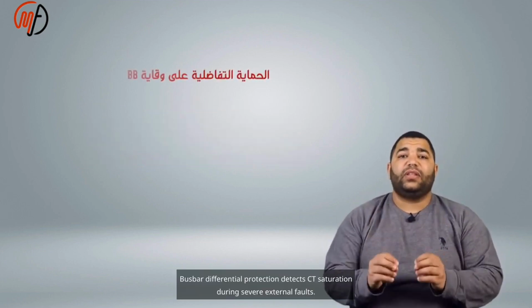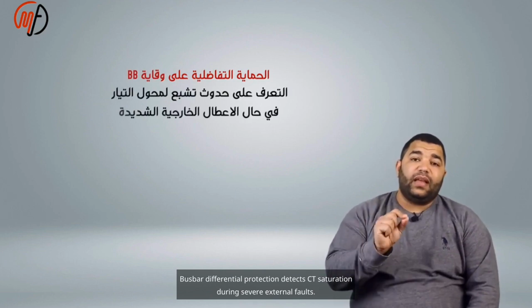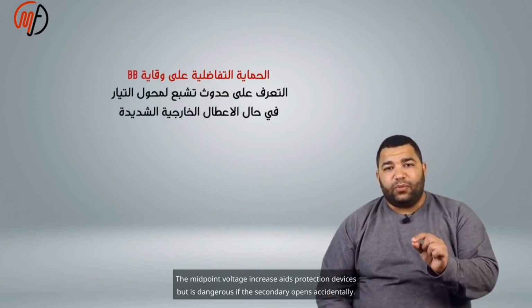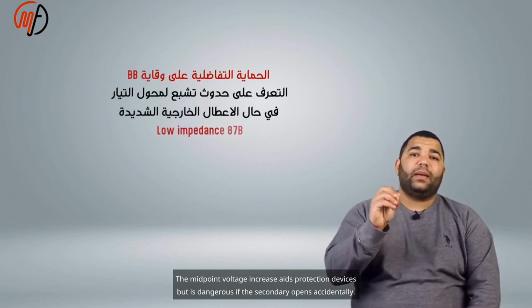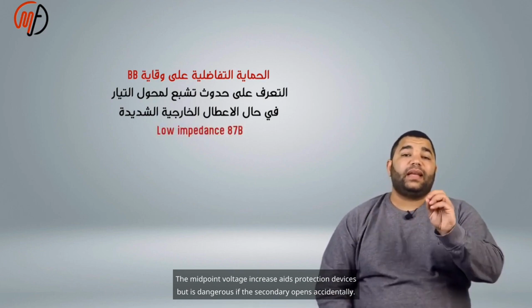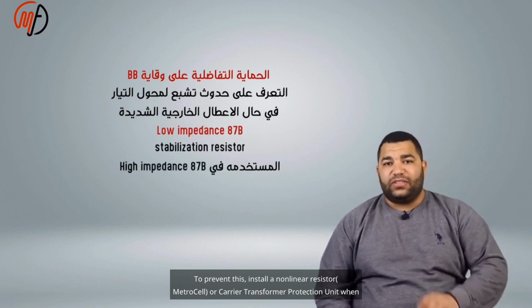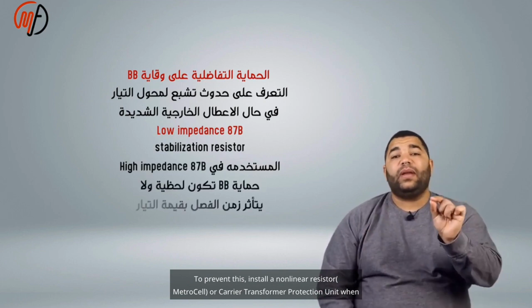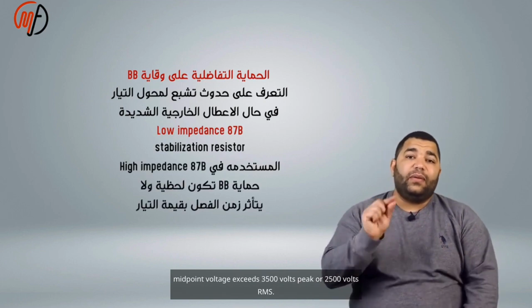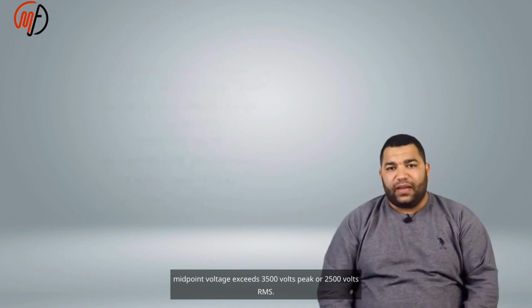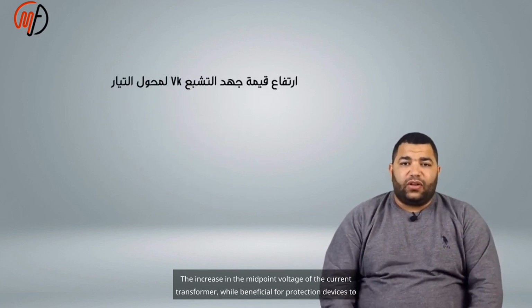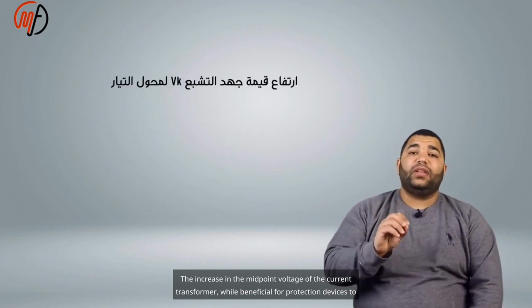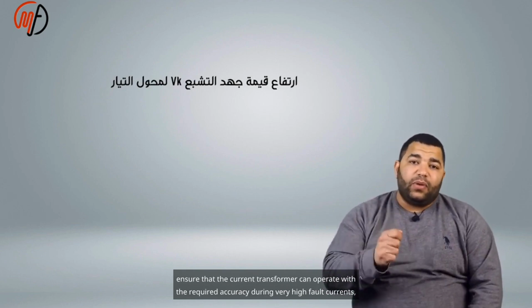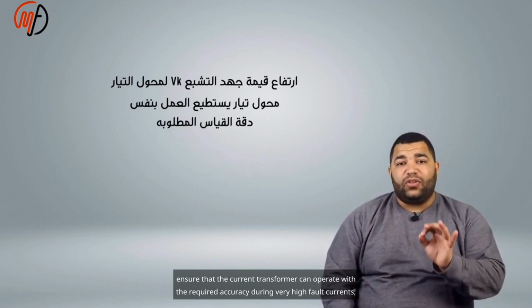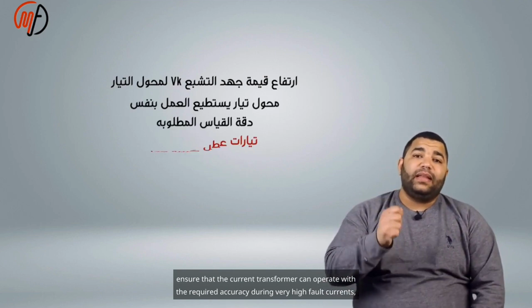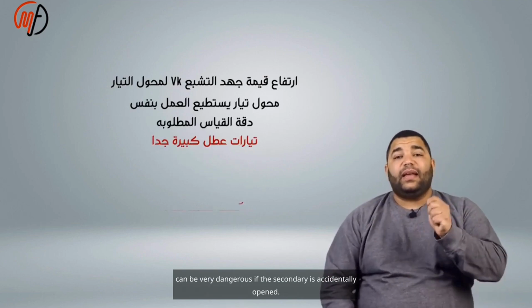Busbar differential protection detects CT saturation during severe external faults. It trips instantly. The midpoint voltage increase aids protection devices, but is dangerous if the secondary opens accidentally. To prevent this, install a nonlinear resistor, Metrosil, or current transformer protection unit when midpoint voltage exceeds 3500 volts peak or 2500 volts RMS. The increase in the midpoint voltage of the current transformer, while beneficial for protection devices to ensure that the current transformer can operate with the required accuracy during very high fault currents, can be very dangerous if the secondary is accidentally opened.